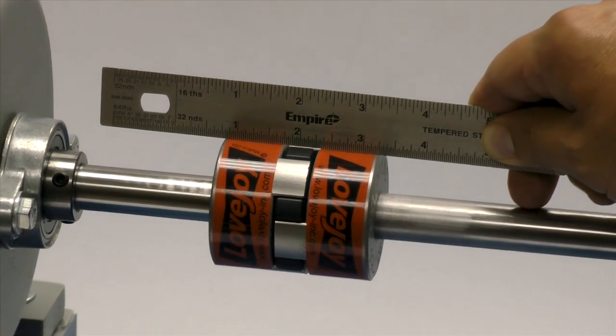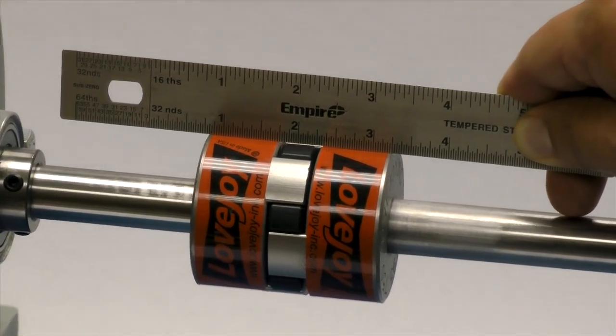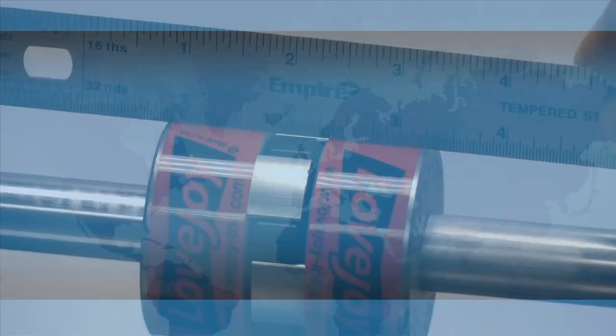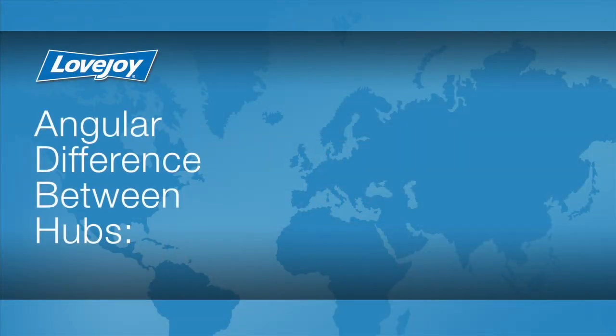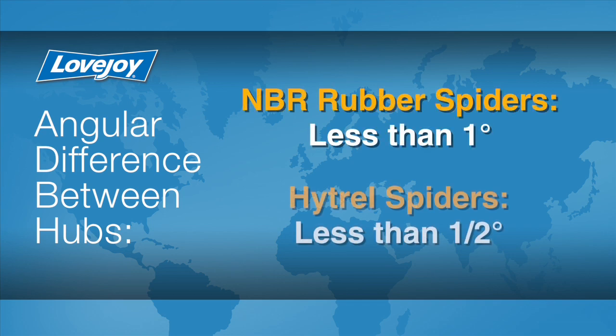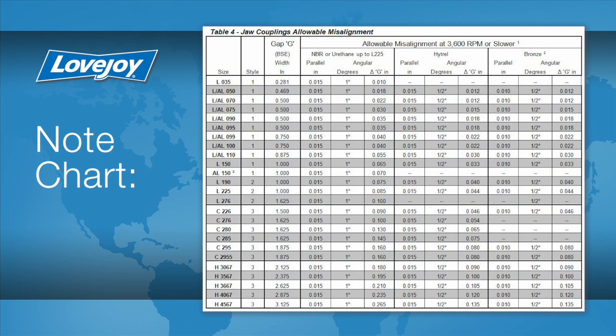The offset between the two hubs must be less than 1/64th of an inch to prevent damage to the coupling. The angular difference between the two hubs should be less than one degree for NBR rubber spiders or less than a half a degree for Hytrel spiders. If the alignment exceeds the allowable amount, as shown on the following chart, realign the equipment to correct this condition.